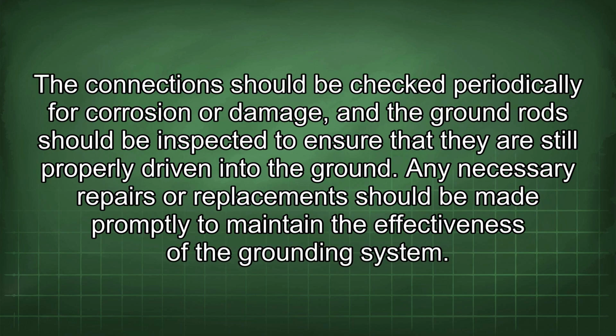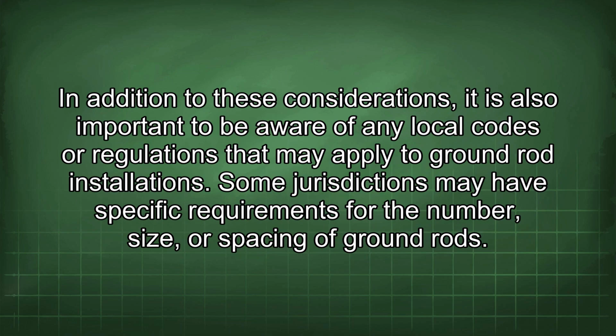A connection should be checked periodically for corrosion or damage, and the ground rods should be inspected to ensure that they are still properly driven into the ground. Any necessary repairs or replacement should be made promptly to maintain the effectiveness of the grounding system. In addition to these considerations, it is also important to be aware of any local codes or regulations that may apply to ground rod installations.